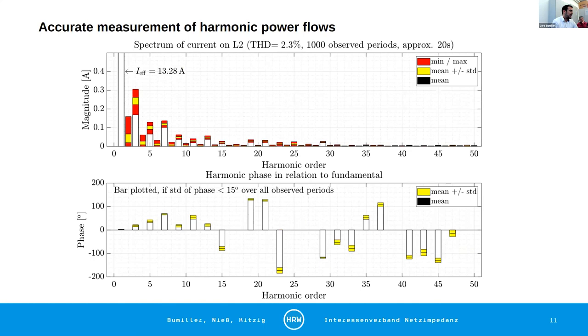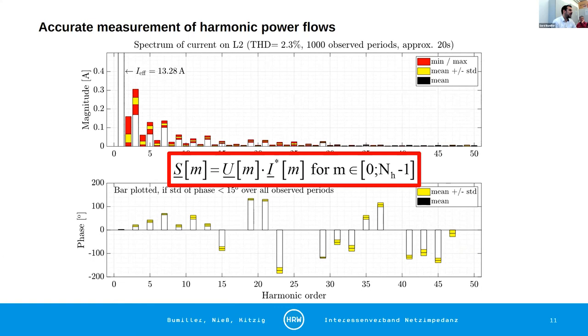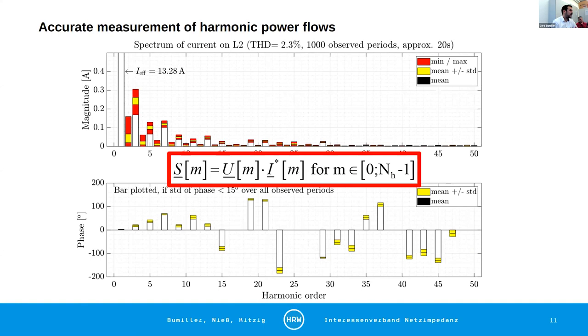We can do this also with current measurement. Now it becomes more important because we can now determine power flows on harmonics. So you should be familiar with this formula, with this equation. And we can now perform for each harmonic M, so M is our harmonic order, we can perform the apparent power, the real power, and the reactive power that are flowing on these harmonics. That's from me. Thank you very much. And if you have any questions, we are now open to listen to them.